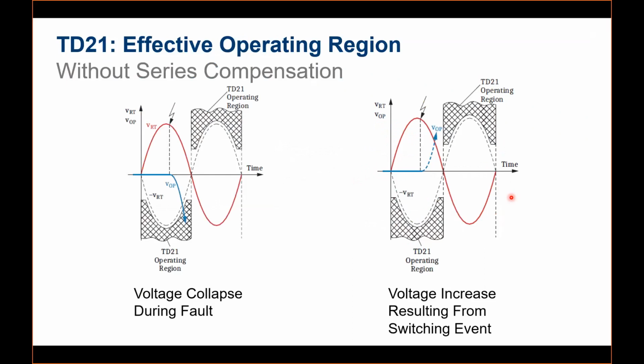One more application we have is special for series compensated lines, because series compensated lines have always been a challenge for conventional phasor-based technologies because of the impedance compensation. The relay will not get the real-time impedance of the line because of the capacitance. Just consider an example without series compensation settings. If you have configured the relay without series compensation, we have an operating region and a restraint region. The operating region for this TD21, and these are all internally calculated operating and restraint quantities. This is like the operating voltage, and this is the restraining voltage.